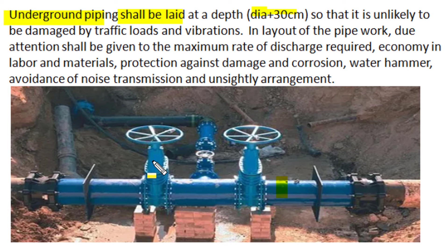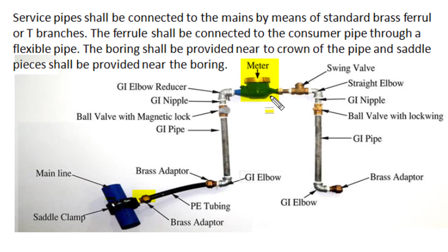Service pipe shall be connected to the main line by means of a standard brass ferrule or T branches. The brass ferrule shall be connected to the consumer pipe through a flexible pipe, and when boring is done on the mainline pipe, it should be near the crown of the pipe, and an appropriate saddle clamp shall be provided over the boring to avoid any leakage and ensure firmness of connection. Water supply should be metered by appropriate arrangement and should have provision for stoppage of reverse flow.